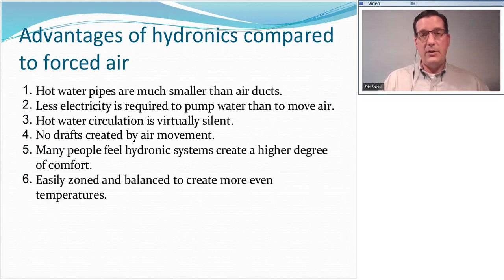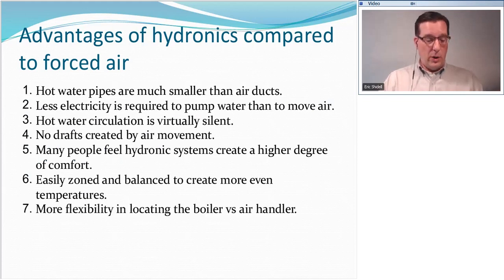Another advantage of hydronic systems is it's really easy to zone them. It's really easy to balance to create more even temperatures through a structure, or to individually tailor temperature settings to different areas of the house or building. We have a lot more flexibility in where we locate the boiler versus where we locate the air handler. On a forced air system, the air handler is preferred to be smack dab in the middle of the building or structure, and that's not always easy to do. And sometimes when we have to put the air handler on one end or the other of the building, it leads to other problems. A boiler, on the other hand, doesn't even have to be in the same building.